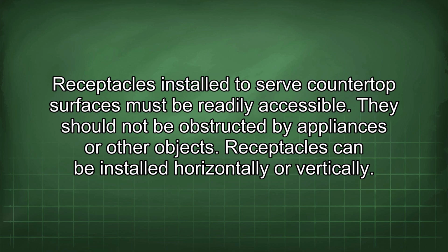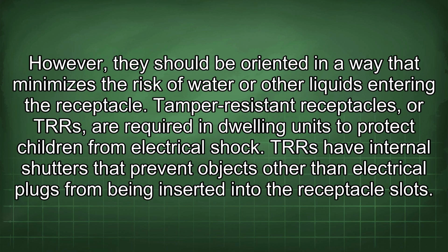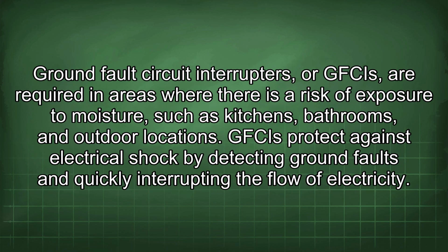Receptacles can be installed horizontally or vertically. However, they should be oriented in a way that minimizes the risk of water or other liquids entering the receptacle. Tamper-resistant receptacles, or TRRs, are required in dwelling units to protect children from electrical shock. TRRs have internal shutters that prevent objects other than electrical plugs from being inserted into the receptacle slots. Ground fault circuit interrupters, or GFCIs, are required in areas where there is a risk of exposure to moisture, such as kitchens, bathrooms, and outdoor locations.